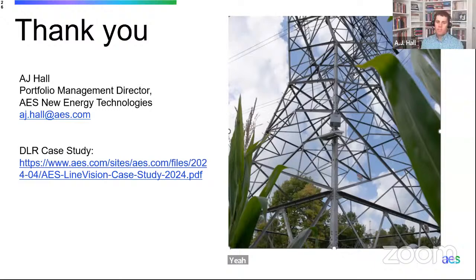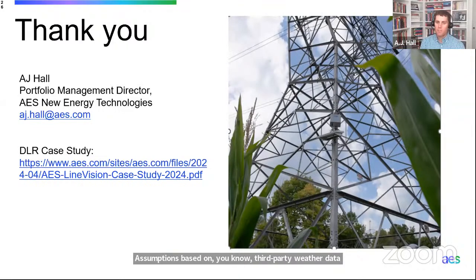Good question, Melinda. AAR, depending on implementation, can unlock additional capacity, but it doesn't give you real wind speed—it's not informed by real sensors in the field. You're still making assumptions based on third-party weather data. It's just a cheaper implementation, software- and procedure-based, as many utilities employ today. There's a cost associated with DLR, so AES is looking at it for our critical lines—we have large 345 kV infrastructure around Indianapolis and around Dayton, Ohio. We're looking at DLR for those lines because of the large amount of power they move and how critical they are from an outage and transmission operations perspective.